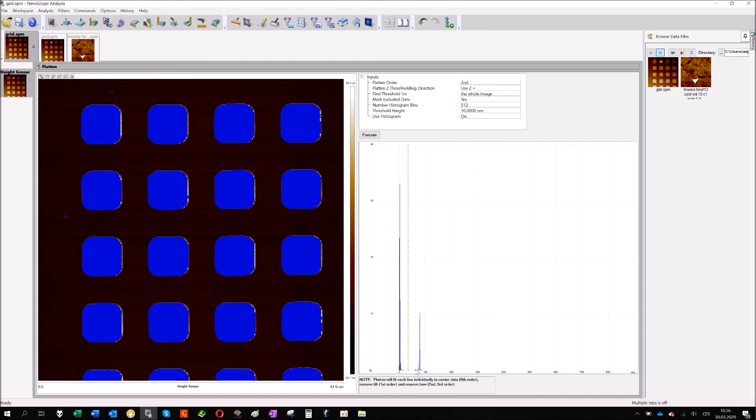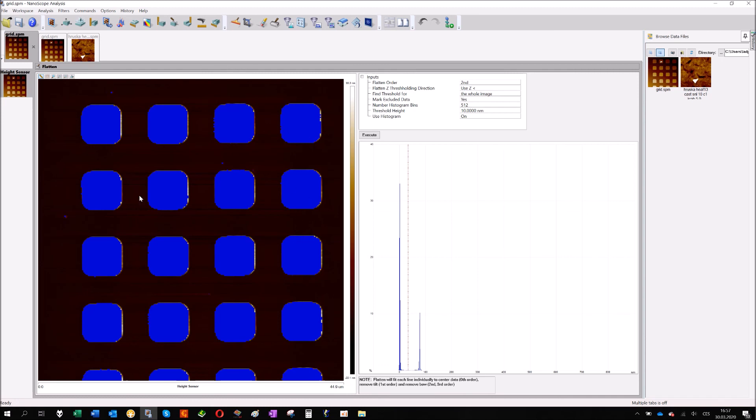I prepared it here and it looks like this. There is the histogram of all points with the height and you can see there is one big peak here around the zero. That's the substrate position. Then nothing and second peak, that's all the features, all the calibration hills. What we are doing, you just mark here the line on the 10 nanometers and we are using all points which are below 10 nanometers for calculation. And all data which are above, I'll just mark it as blue. And you can see all the big features are marked, but also a few dust particles are marked as blue and it will not be taken into account for calculation.